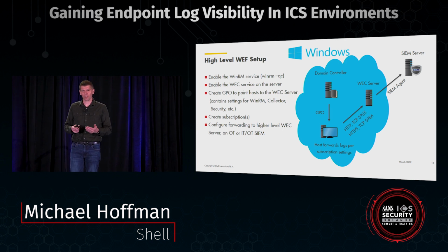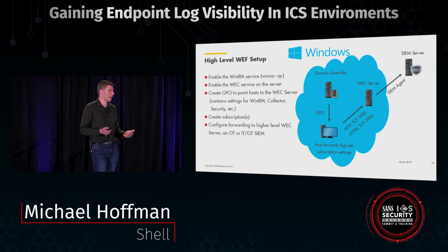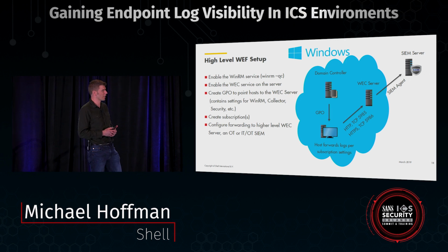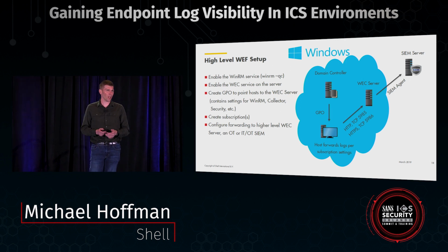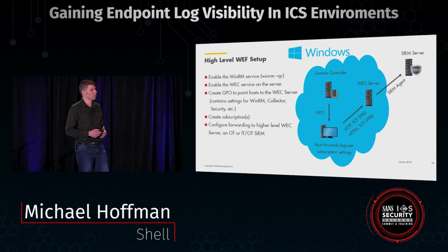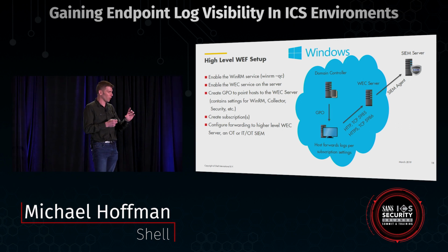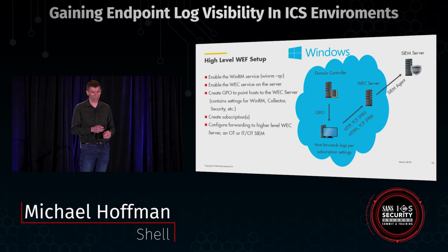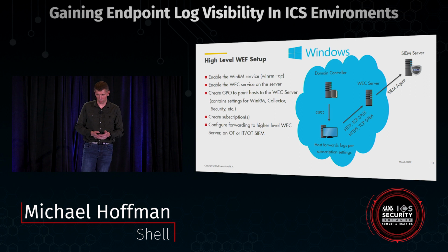And we'll also discuss the communication aspect and firewalls. So we've struggled a lot in the past with firewalls, and especially with DCOM. DCOM, as most of you know, is also OPC DA. It's OPC classic communication. So I would almost say that everyone in this room is running DCOM, DCE-RPC protocol, and those kind of things. But with this, you can really lock down your firewall rules for logging. When you look at the generic setting, which is HTTP, and we'll talk about that a little bit more in a second, that's HTTP from the outside as the transport protocol. But when you start to take that packet apart, that's just the frame of it. And then when you dig into it, it's actually an encrypted communication. And again, that's one port. It's one direction. It's very simple to set up the firewall rules in this environment for logging.